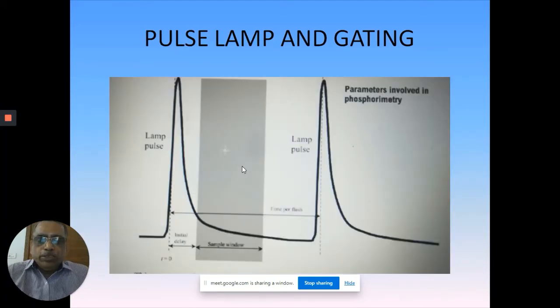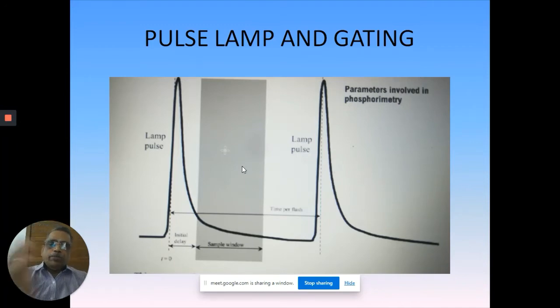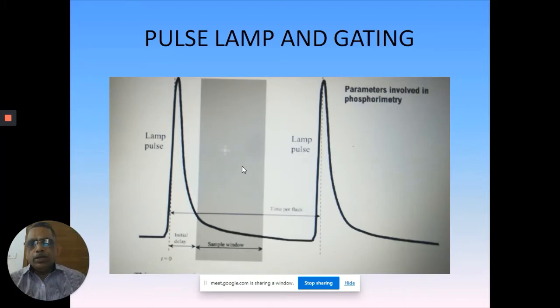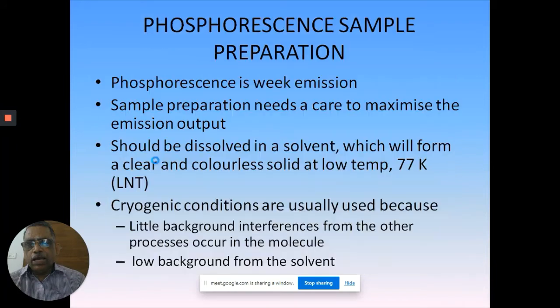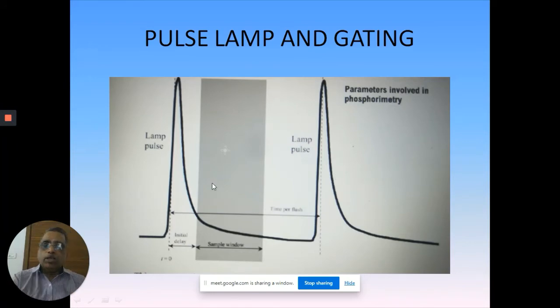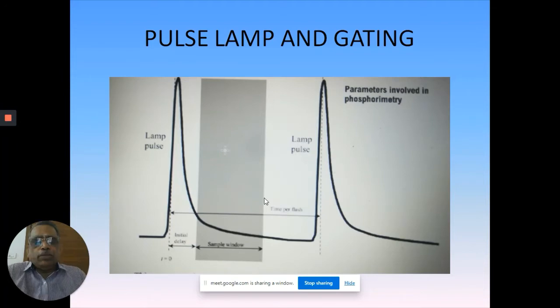Some new machines go for a pulse lamp instead of chopping in front of the light source. They give a separate light source for phosphorescence measurements that is itself a pulse lamp - some pulse even the existing lamp, though that reduces lamp life. Electronically you can pulse the lamp, and once the pulse disappears in intensity, you start measuring phosphorescence. You can adjust the spacing between pulses, pulse width, and gate measurement window - this gives a lot of flexibility to measure phosphorescence parameters.